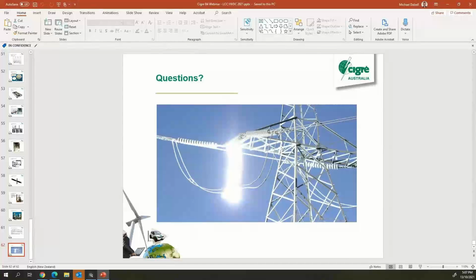Wind farms, solar doesn't count. So that's probably where the LCC is going to be really eclipsed by the VSC as the grid gets less of that traditional generation in it. LCC is going to become less and less appropriate. You start to have really serious problems with commutation failures once you get to these really weak grids.